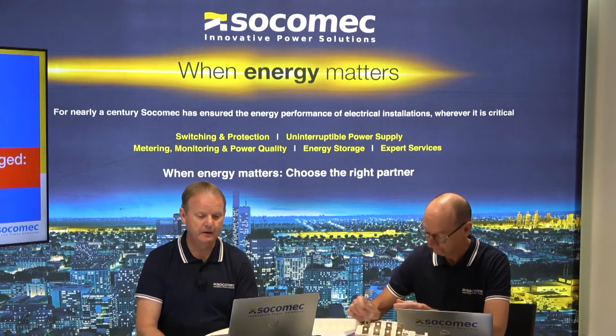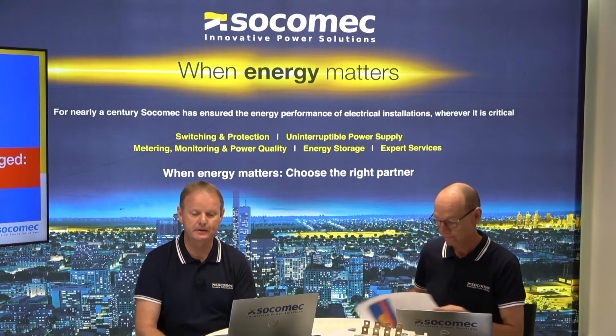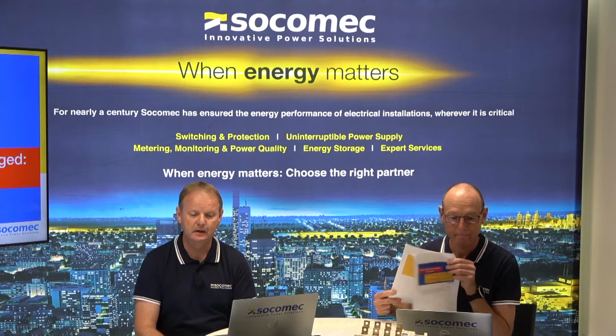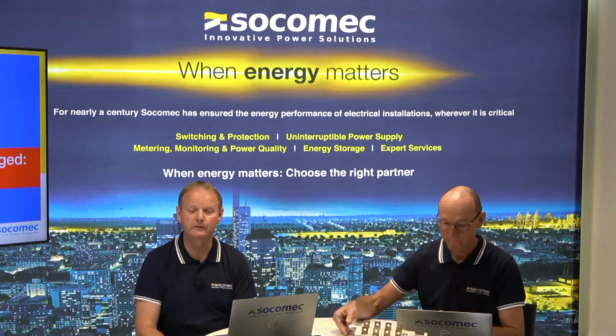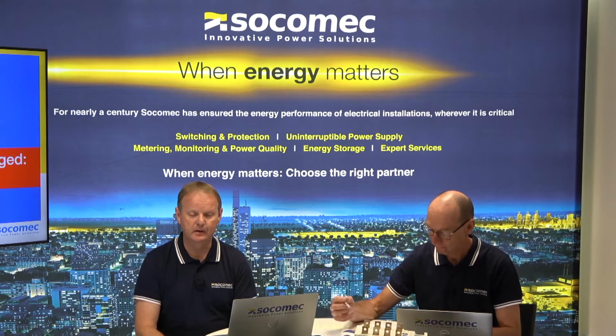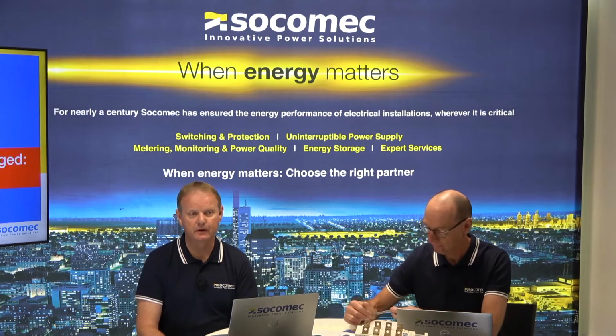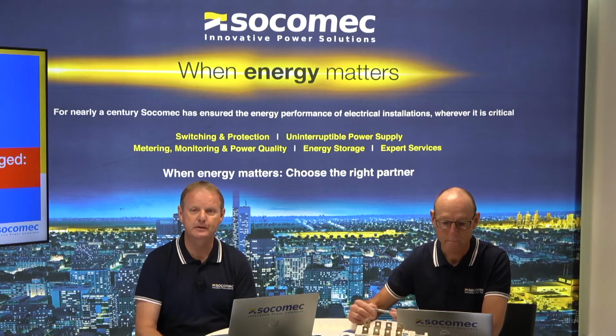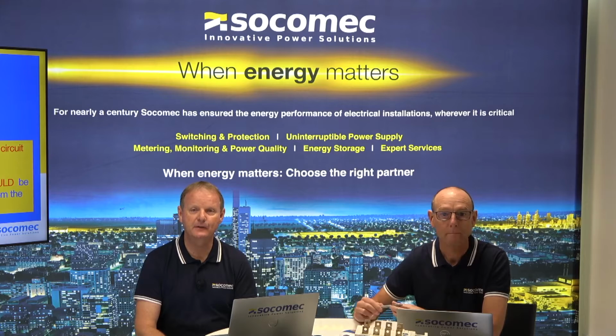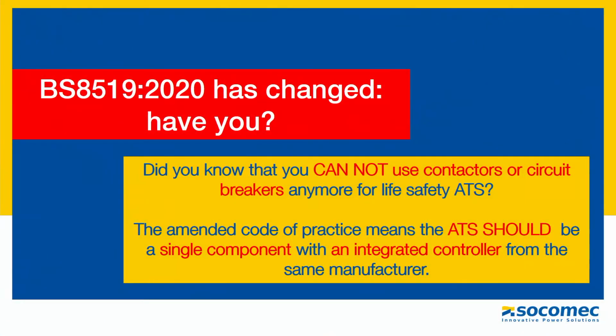What we're going to show you today is a major change in the British installation standards with regards to life safety services. This will be an ongoing series over the next 6 to 12 months, so please keep an eye out and we'll come back to you with further details. So, BS 8519-2020 has changed. The major change really now is that, did you know that you cannot use contactors or circuit breakers anymore for a life safety ATS?